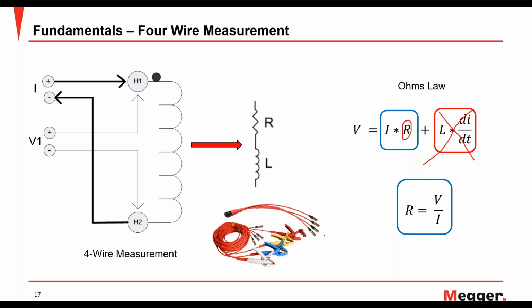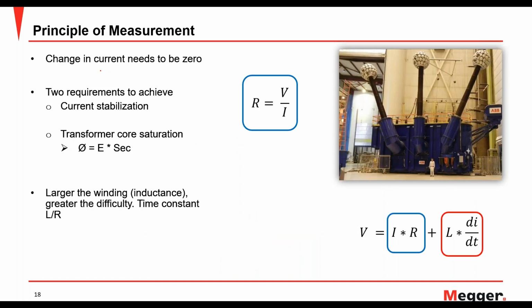These are the typical leads that come with your instrument for three-phase. You have your three phases and a neutral in some cases. So definitely your Y winding when you need one. Principle of measurement, the change in current needs to be zero. This is important. A lot of people just take winding resistance measurement spot on, and there you go. It's not like that because your resistance keeps jumping around until your current is stabilized. How do you attain current stabilization? By saturating the core of the transformer. The larger the winding, the greater the difficulty. That means it's harder to saturate a bigger transformer rather than a smaller transformer.